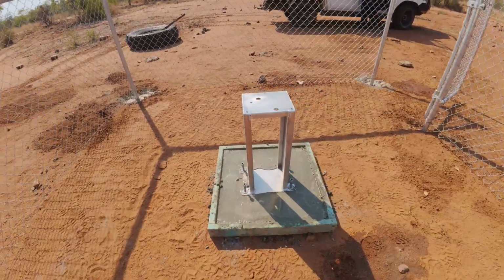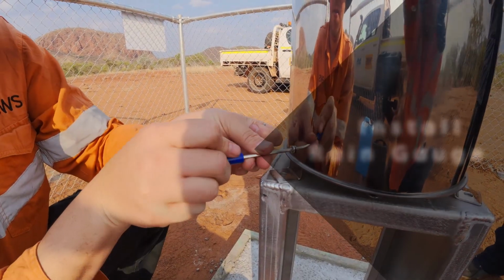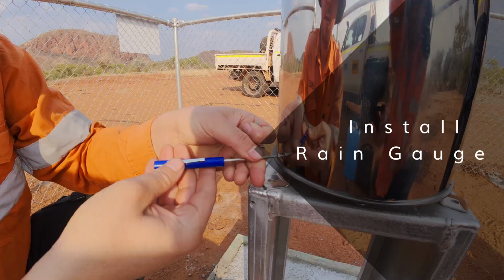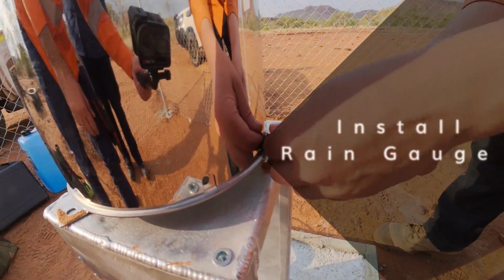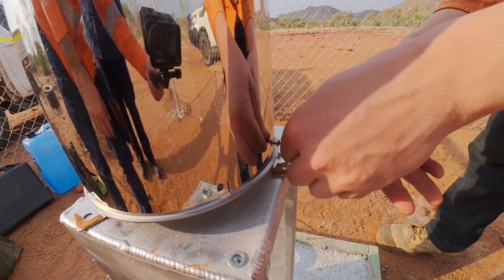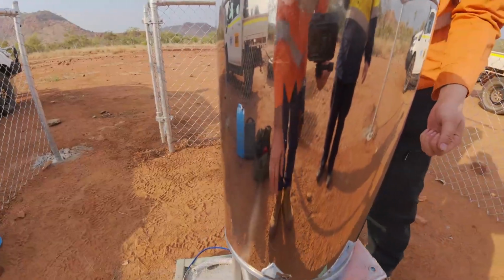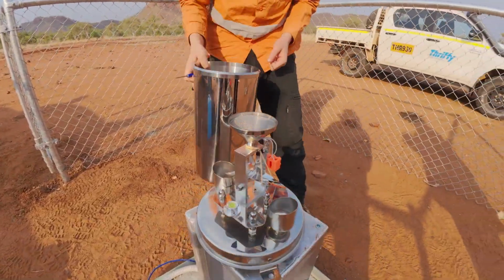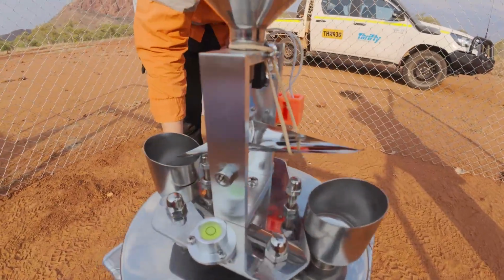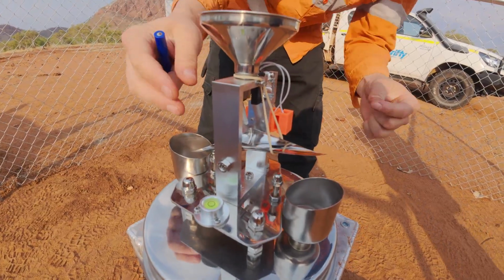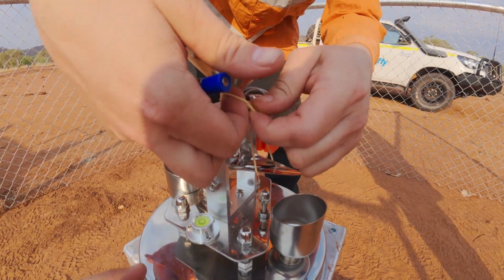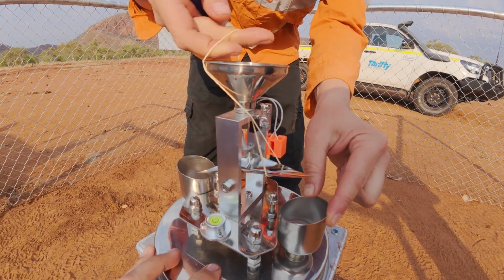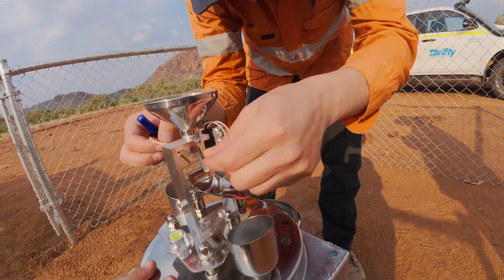So back on site the next day, it's time to assemble the station. Start by removing the outer cowling of the rain gauge by removing the 3 screws near the base. Gently lift the cowling upwards, revealing the tipping mechanism. Absolutely remember to remove the rubber band around the tilting mechanism and ensure it moves freely, otherwise even if it rains, you'll only read zeros.